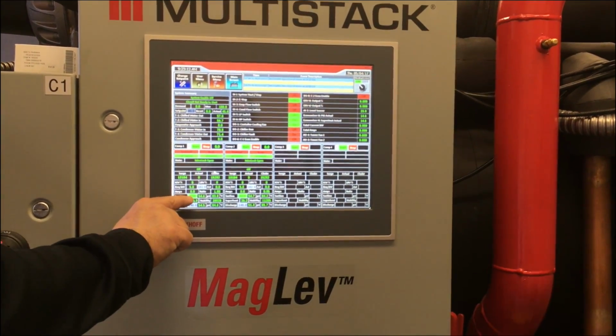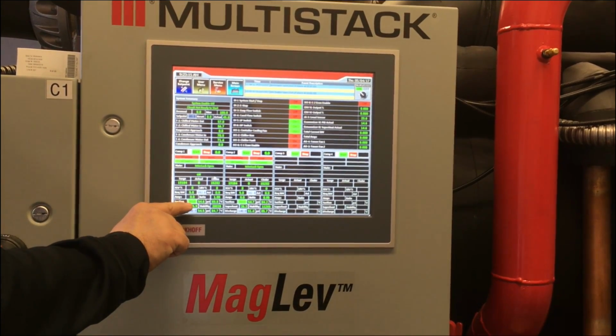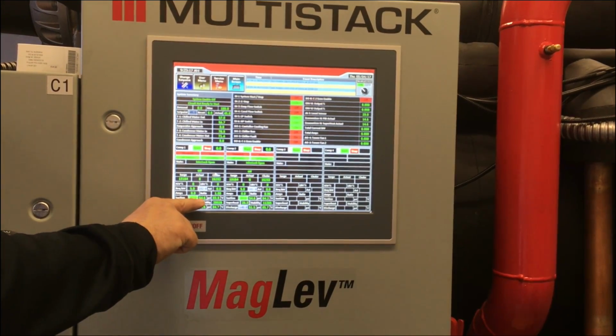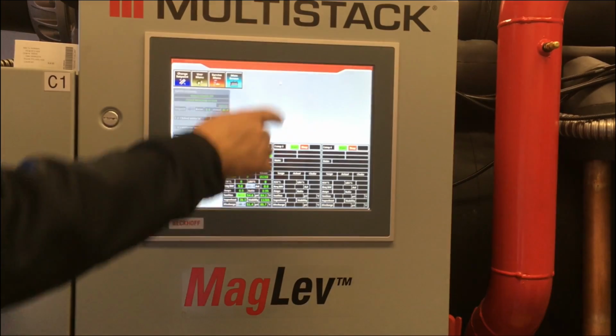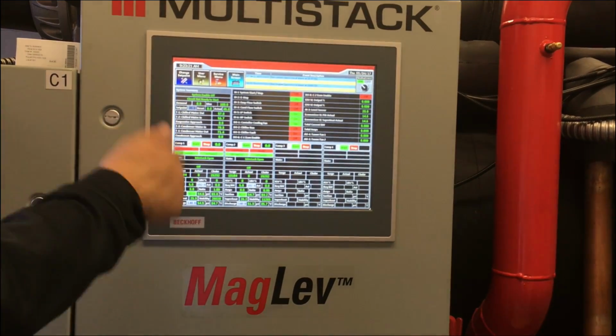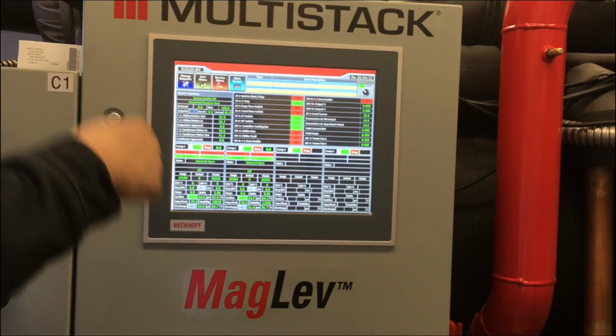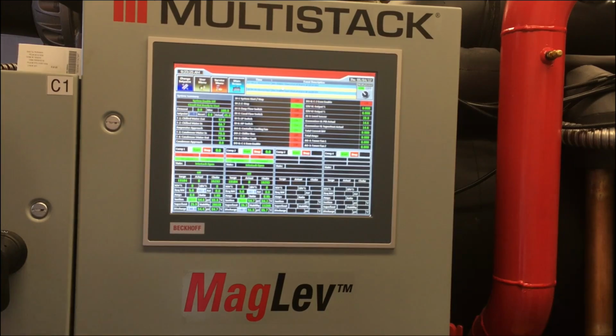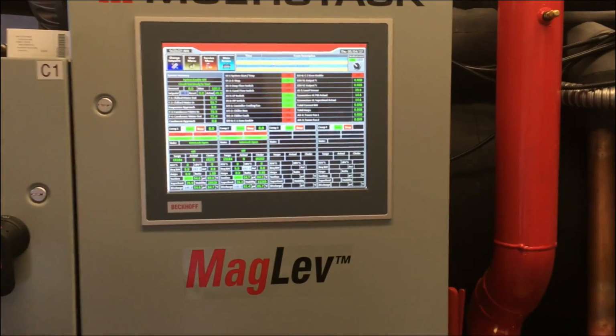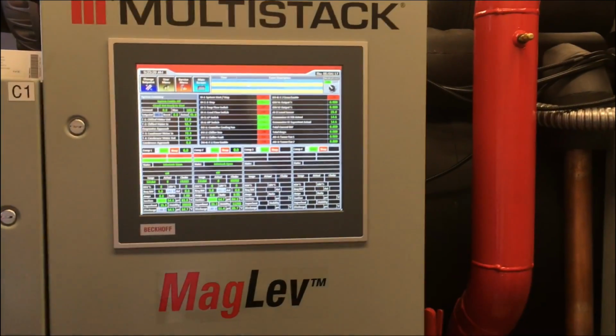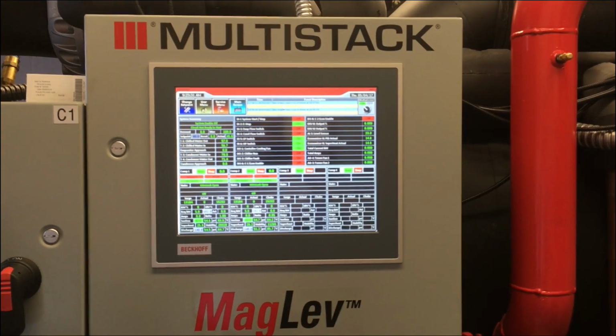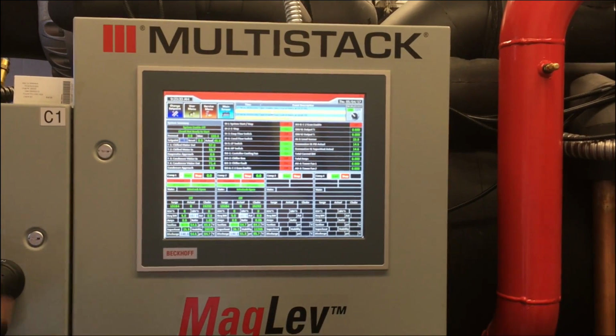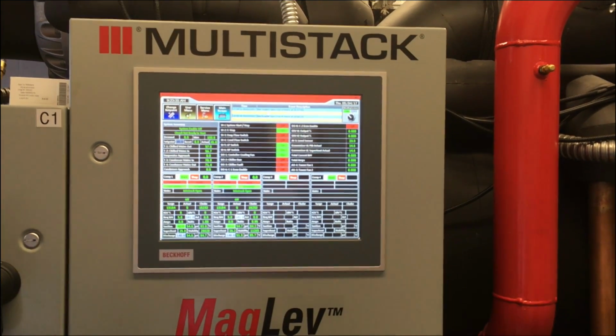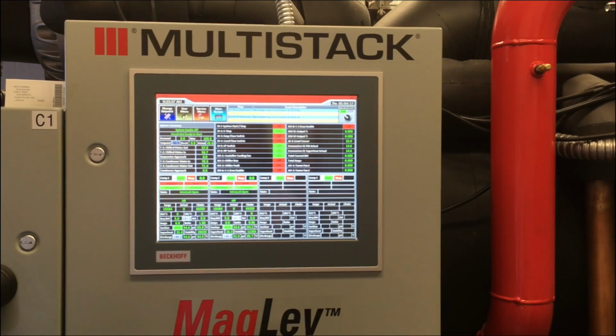So if that number, right now let's say that number is 42 in green. If this number 56 is higher, it's going to keep driving that compressor harder and harder and harder to try to get it down to that 42 number. If it goes under it, it's going to stop and back it off. And that's how it determines the speed of the compressors. So the level sensor works the valves, the suction set point works the compressors. They all work in one kind of harmony to make this all happen.